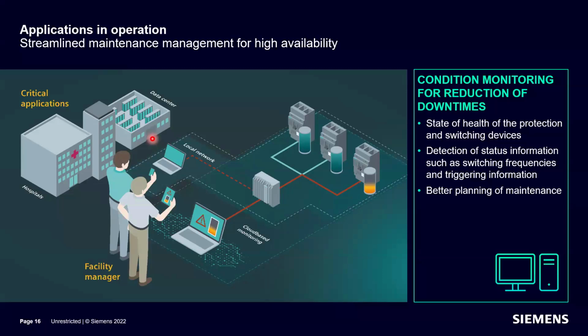So those information, probably the contact health status of the air circuit breaker - air circuit breakers are maintainable, so information on when the pole assemblies are required to be changed can be gathered over this controller or IoT device, giving information that at certain times you have to be prepared for a change of the pole assemblies. These are the informations used for predictive maintenance or condition monitoring, given by sensors like ACB and MCCBs.